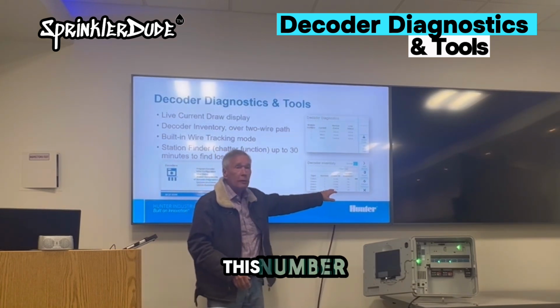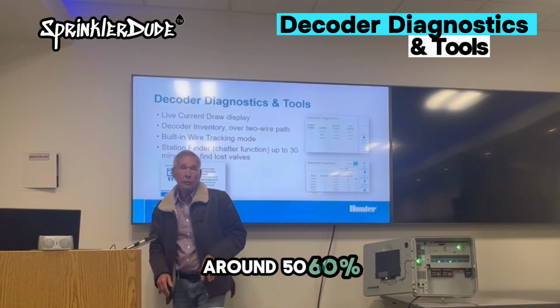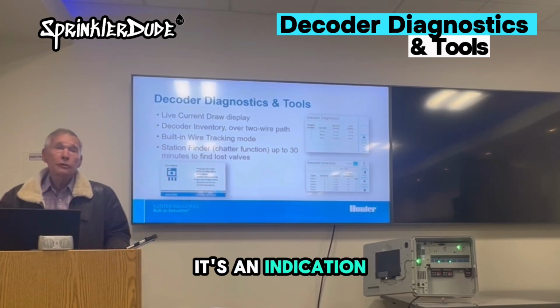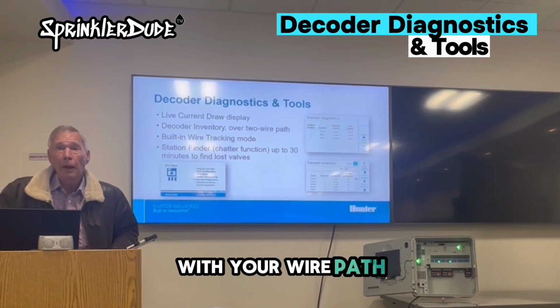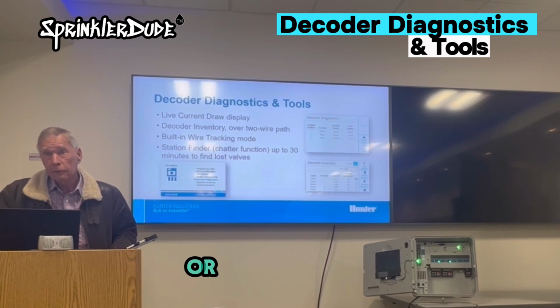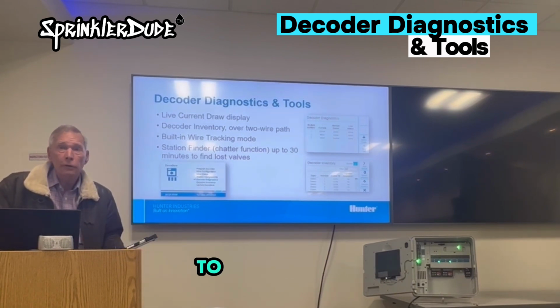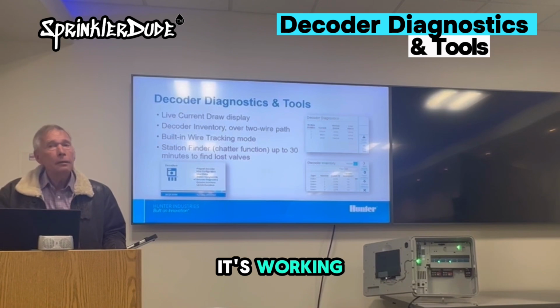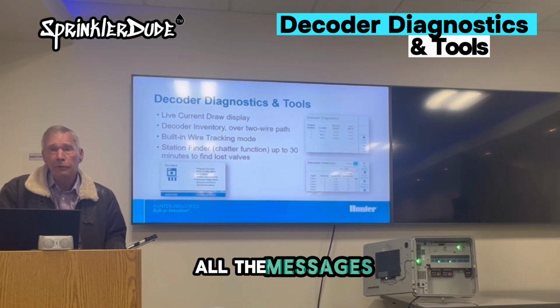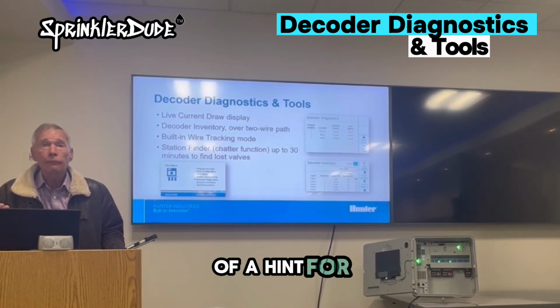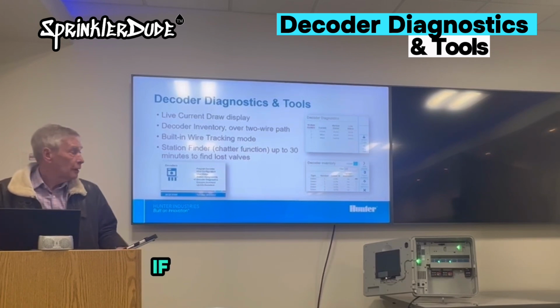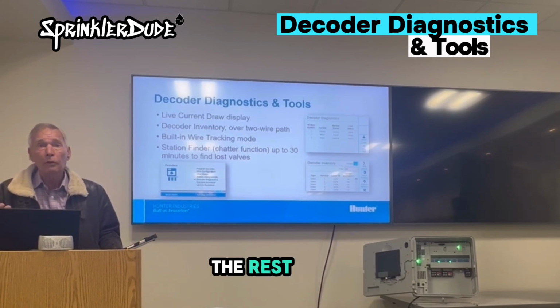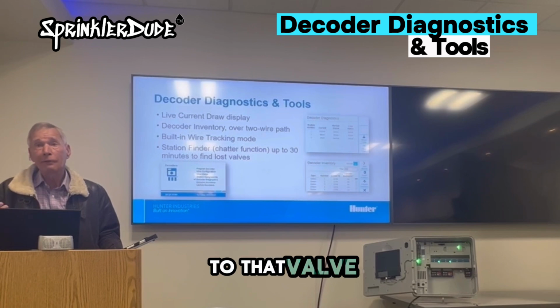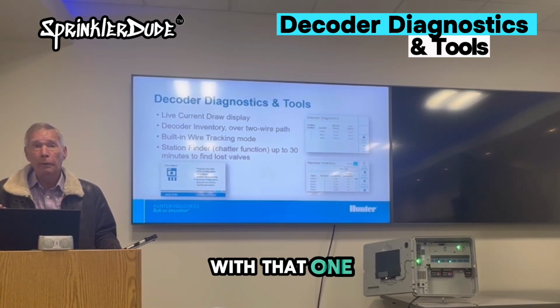But if you see this number getting down around 50, 60%, it's an indication that something is wrong with your wire path, that you've got crappy connectors, or you've got a nick in the wire with a short to earth ground. It's working, but it's not getting all the messages. So it's kind of a hint for preventative maintenance. If one of those is at 50% and the rest look pretty good, I'm going to go to that valve box and see what's going on with that one.